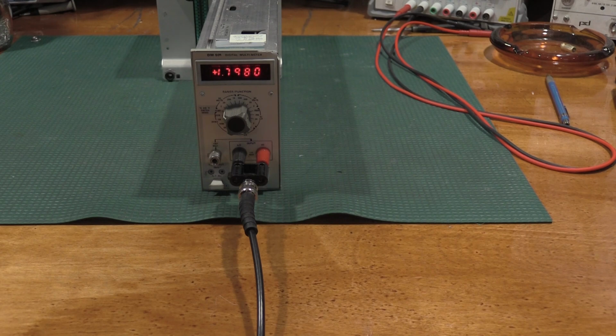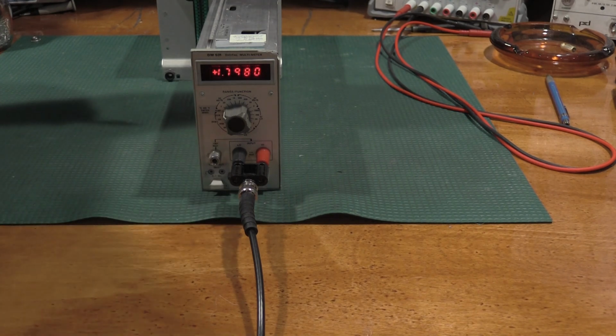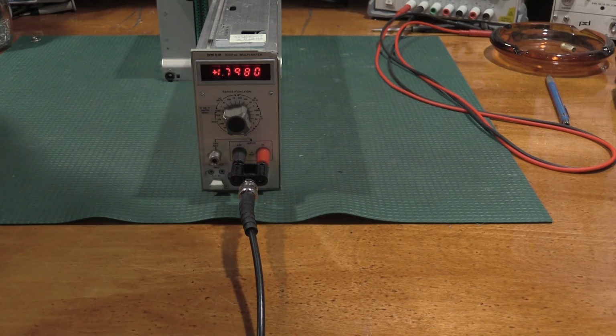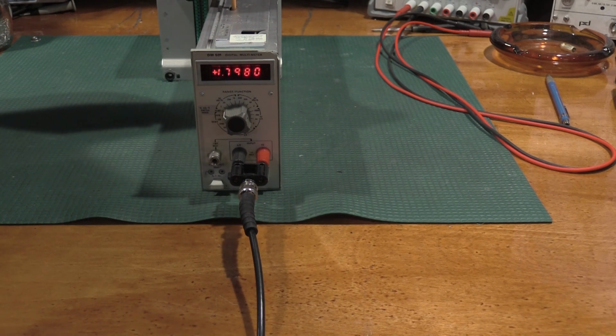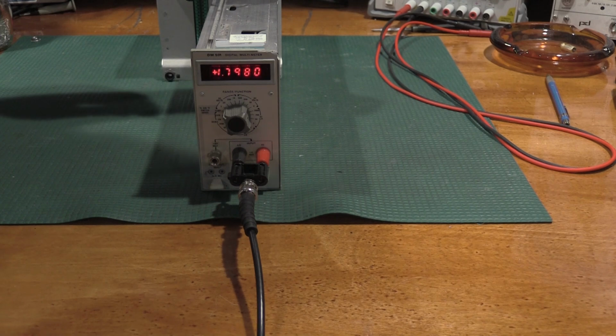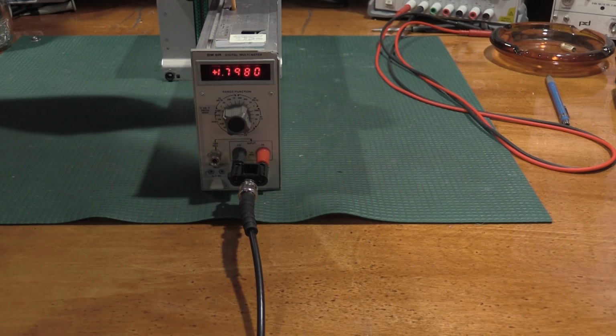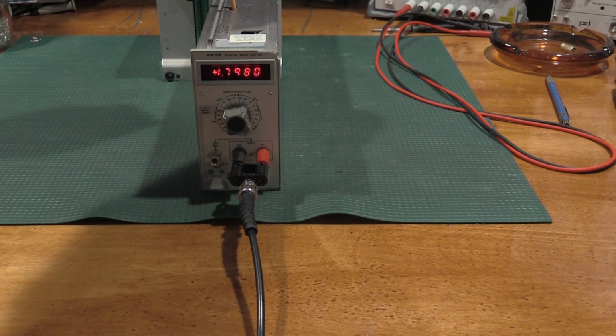All right, this is the middle of the 10-turn potentiometer up at the top. So we're just going to get a tuning tool on that. This should also tighten up all the ranges, because all the ranges are based on this adjustment. So with this being off, everything will be off, and we're going down, so we actually got to go the other way.